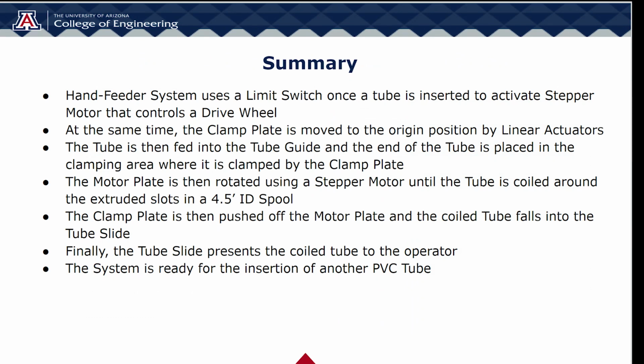So moving on to our summary, the hand feeder system uses a limit switch that is triggered by a tube being inserted. Then a drive wheel pushes the tube into the tube clamp, which is clamped by linear actuators. After that, a stepper motor begins to rotate, coiling the tube.